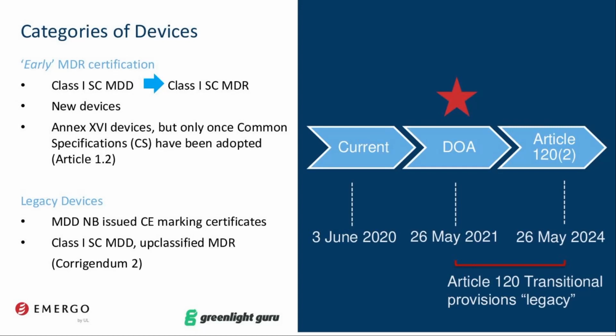What would be considered legacy devices, and this term was previously used in MDCG Guidance 2019, but we feel it was defined a little bit more formally in the MDCG 2020-6 document. That defined legacy devices as devices with CE marking according to the MDD or AIMDD. These legacy devices are legacy at the point of date of application. So that's kind of the concept. But legacy devices would be your products with MDD notified body issued CE marking certificates, or these category of the Corrigendum 2 products, which are Class 1 self-certified by the MDD and upclassified by the MDR.